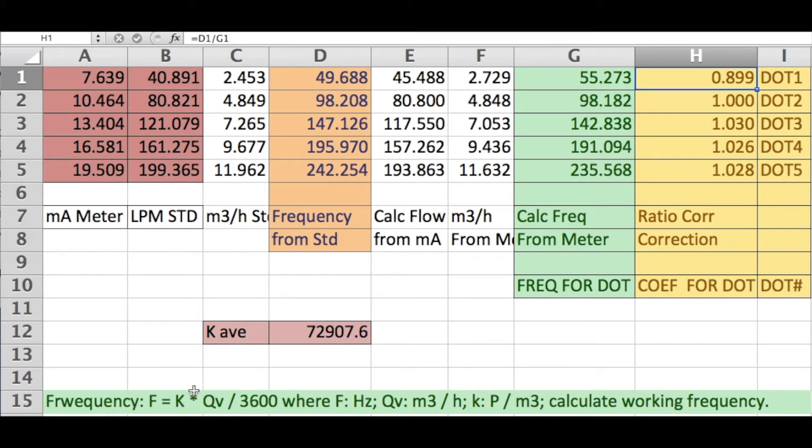Here is the frequency equals k times qv over 3600. qv is cubic meters per hour, and k is this number written on the meter. So that's how we calculate these frequencies. So we only need to put these numbers in. So I'm going to now show you how that's done on the meter.